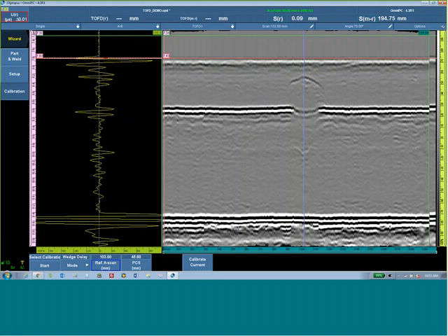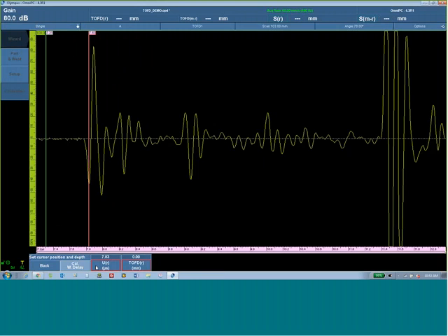I have everything I need to calibrate currently here, but we'll step one more distance here just to see the wizard step. The software is assuming that the PCS is known and valid. So I need only set the position of the lateral wave to redefine the wedge delay at 0 millimeters or 0 inches on the component.